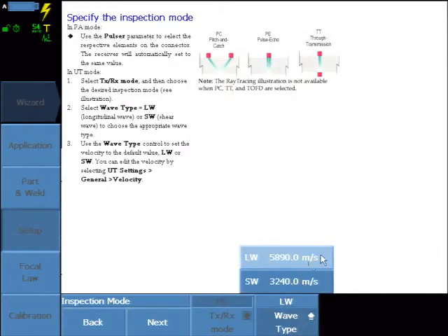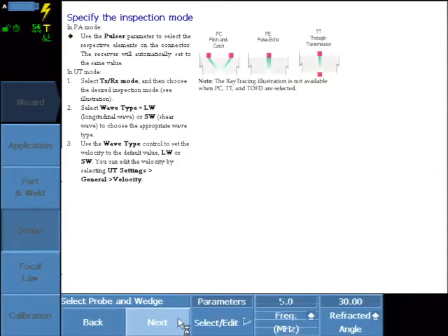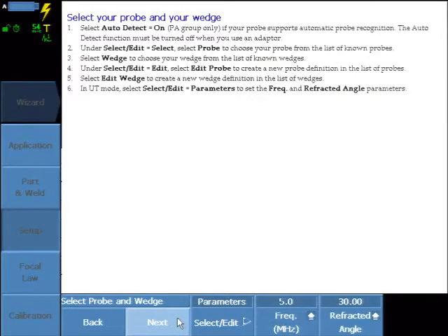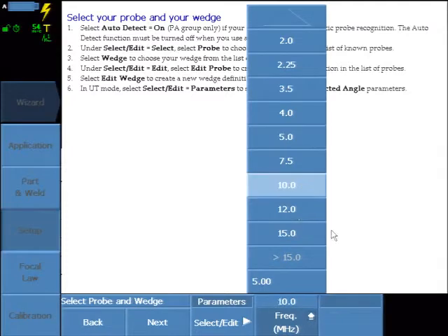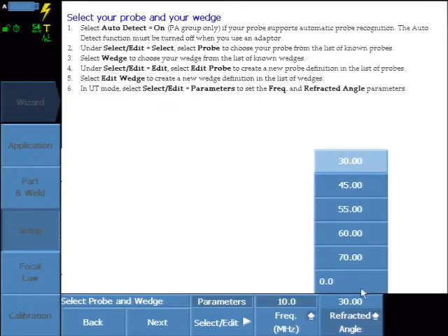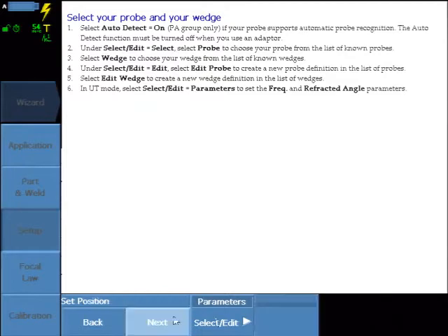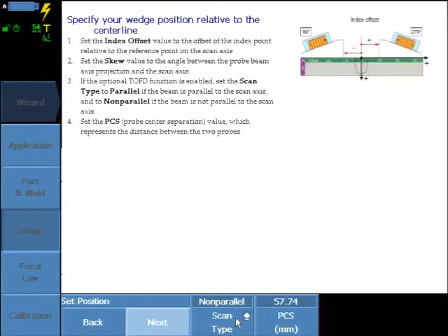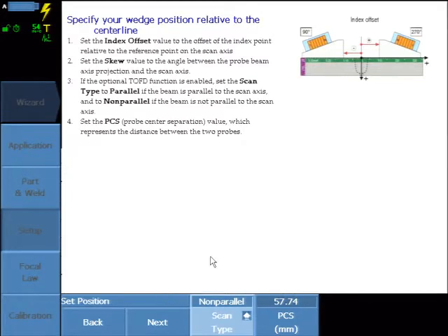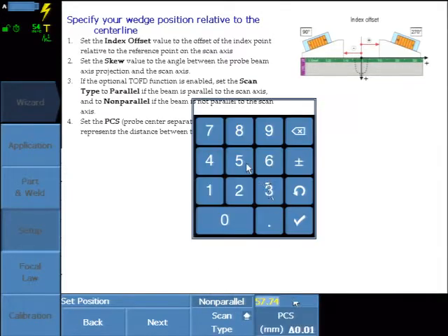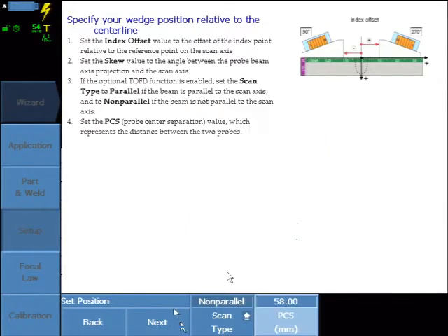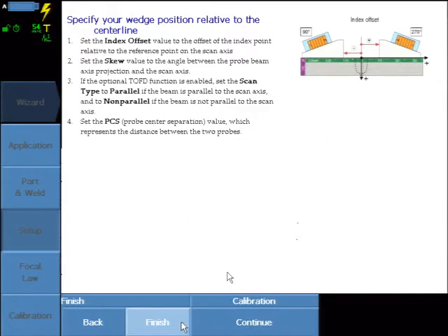Select Longitudinal Wave. This is the Carbon Steel Velocity that came from the Part Wizard setup. Select the Probe Frequency and the Inspection Angle. Select either scanning non-parallel to the weld line or parallel to the weld line, and enter in the calculated PCS. And select Finish.